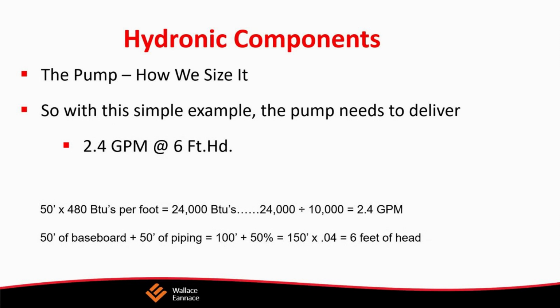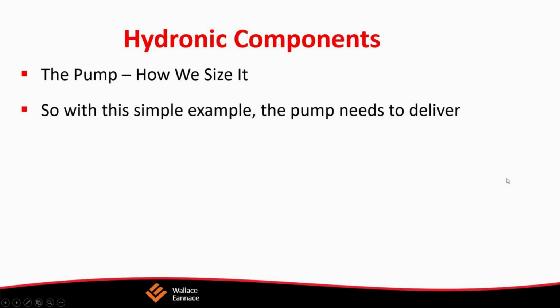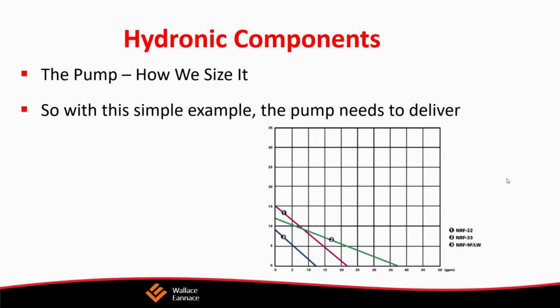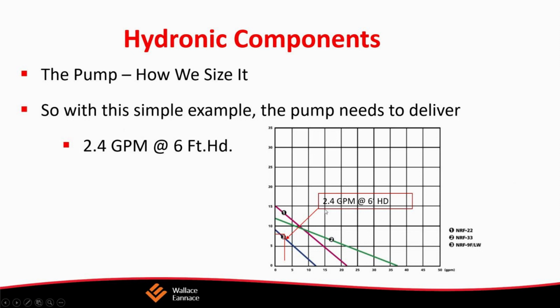What we really only care about is the longest distance of pipe that we need to get water to. What's the furthest piece of radiation? So with that, we add 50% to that as a rule of thumb for fittings. Keep in mind that elbows add the equivalent of 5 feet of distance. Tees also add to it, as do elbows, and elbows and tees will add as much as 50%. So we just round that number off. If we have a distance of, say, 100 feet and then we add 50%, we then have 150 feet. We multiply that times 0.04, and that gives us the required head.